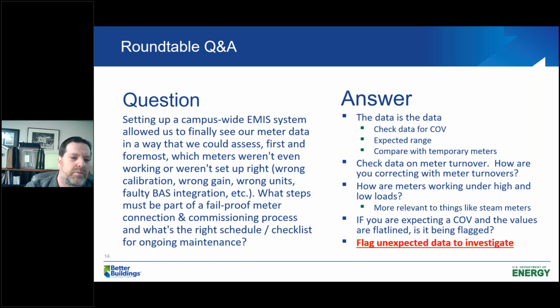Another example is verifying how meters are performing under high or low loads. Steam meters, notoriously, if they're sized for a certain range of steam load, may not accurately indicate how much steam is going through when under a very low load. So I'd focus on the steam meters as a potential issue. Flatline data: are you continuously checking the data for flatline? This may be an indication that there's no consumption, or that there is a problem with the data collection, but not the meter itself. So set up rules to flag flatline data and null values, which can be an indication of a communication issue with the meter. There needs to be investigation of what's going on.